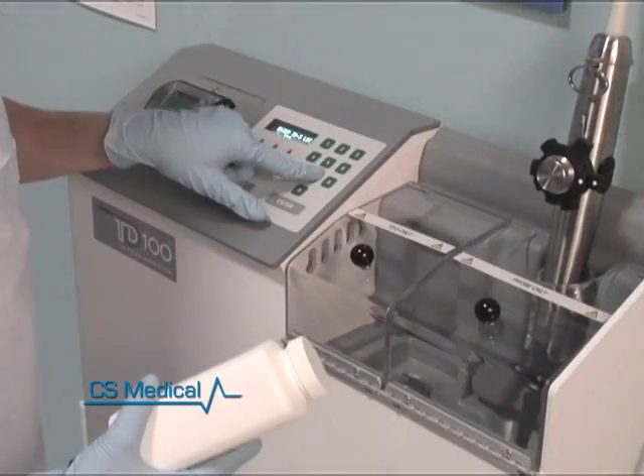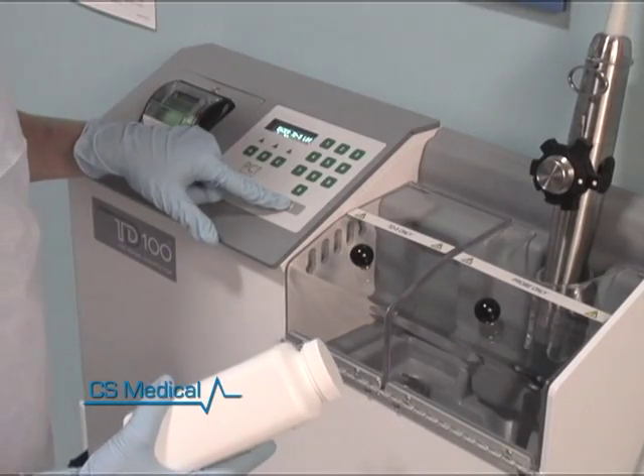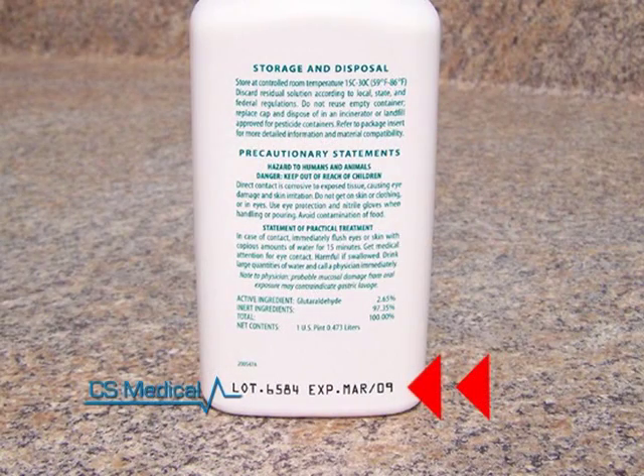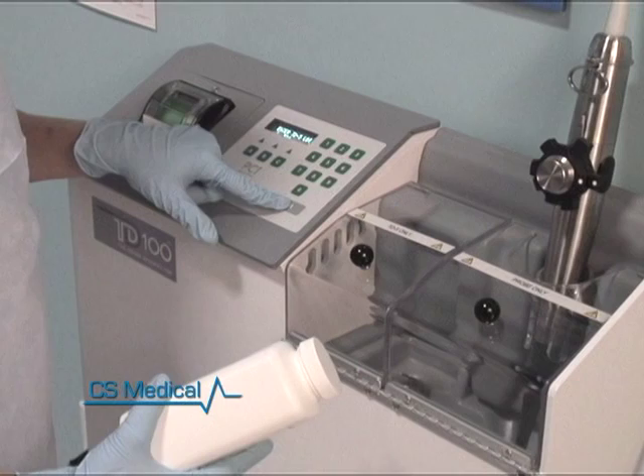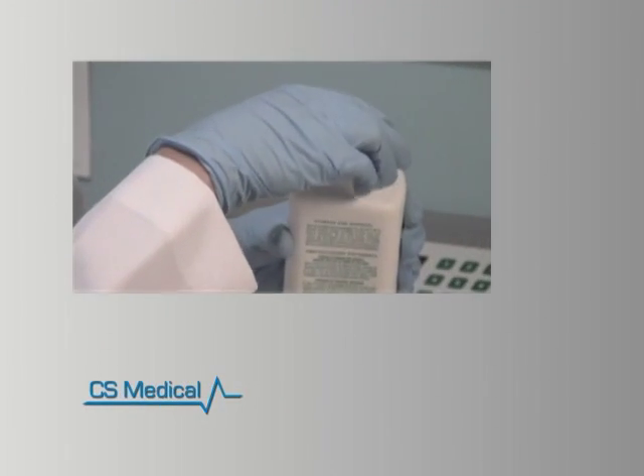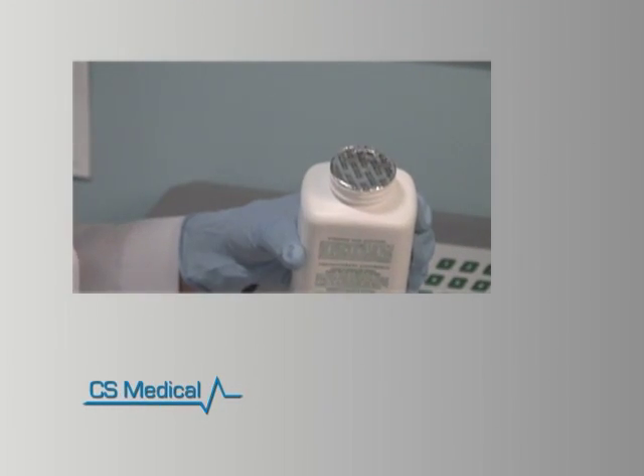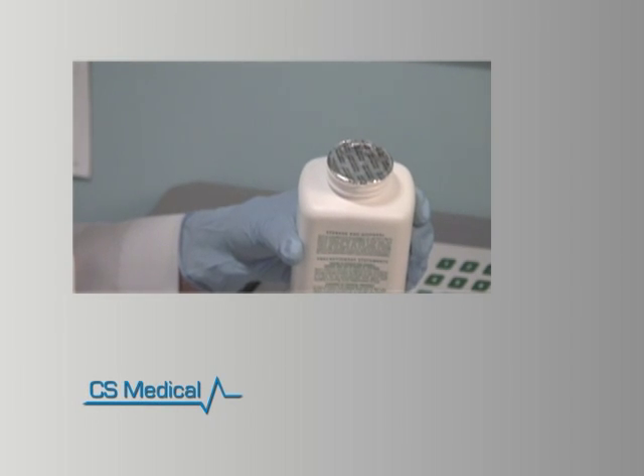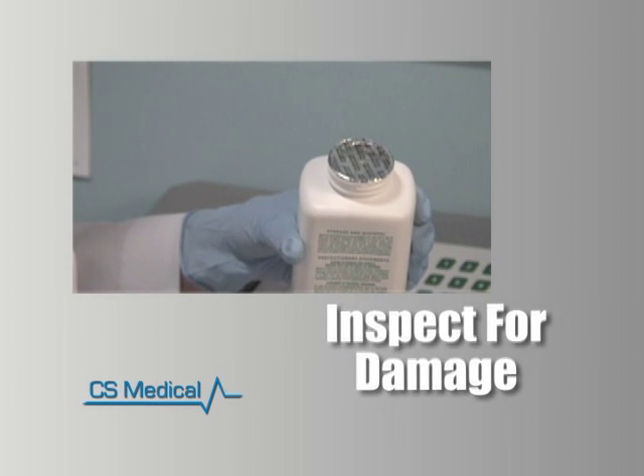Next, you will be asked to enter the TD5 lot number. Located on the back of each TD5 bottle is a lot number. Enter the last 3 digits of the lot number and then press Enter. Remove the screw cap from the top of the TD5 bottle, carefully inspecting for any damage to the foil seal. Damaged bottles should not be used in the TD100, as the TD5 is a measured dose of disinfectant, and a damaged bottle may or may not have the proper dosage or strength.